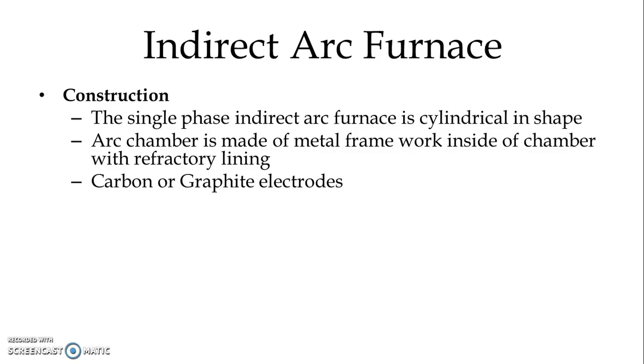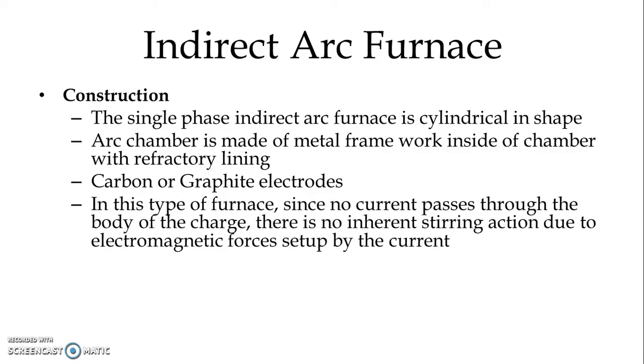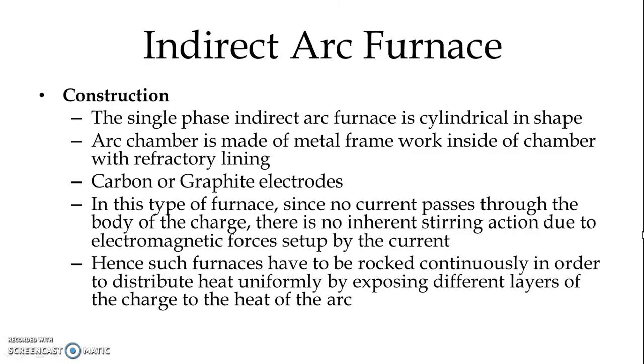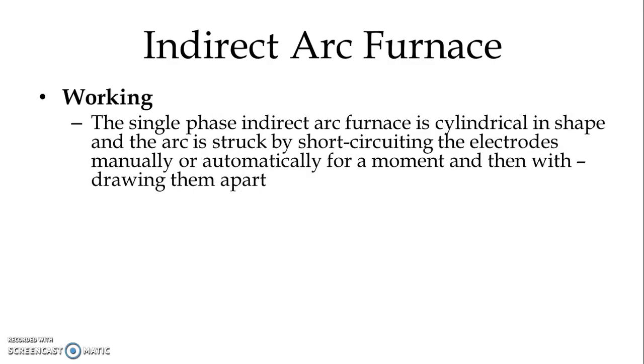Carbon or graphite electrodes are used. In this type of furnace, since no current passes through the body of the charge, there is no inherent stirring action due to electromagnetic forces set up by the current. So stirring action is not possible in case of indirect arc furnace. Hence, such furnaces have to be rocked continuously in order to distribute heat uniformly by exposing different layers of the charge to the heat of the arc. For that, rocking wheels are provided and we continuously rock at different angles as the melting process goes on.